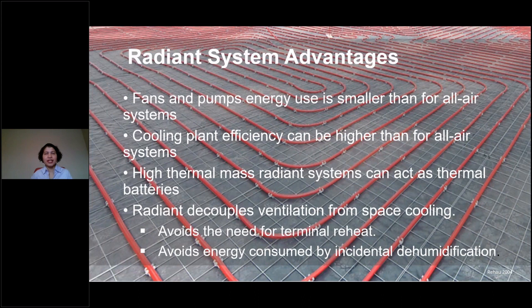Radiant systems use radiant piping to cool or heat the building. Since they decouple ventilation load from the space cooling load, there is tremendous energy savings in fans and pumps. You can avoid terminal reheat, saving on fan energy as well as pumping energy, and the overall cooling plant efficiency is higher compared to all-air systems.